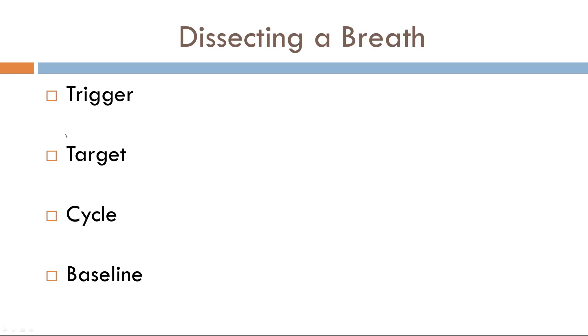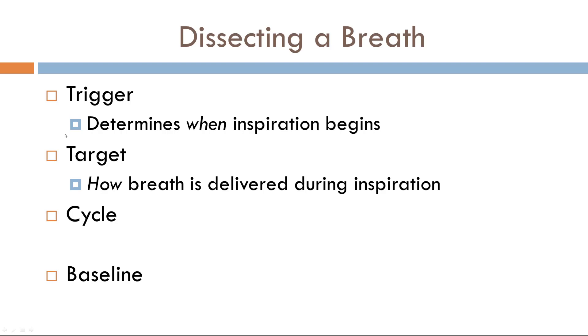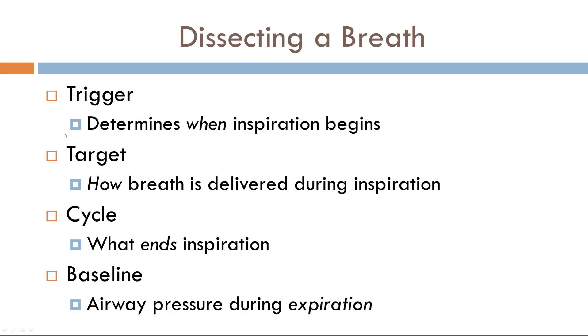The trigger variable is the variable that determines when inspiration begins. The target is how the breath is delivered during inspiration — is it delivered fast or slow? The cycle variable is what tells the ventilator to stop inspiration, what ends inspiration. The baseline phase is the airway pressure during expiration. Importantly, the trigger, target, and cycle phases are all during inspiration, while the baseline phase is during expiration.